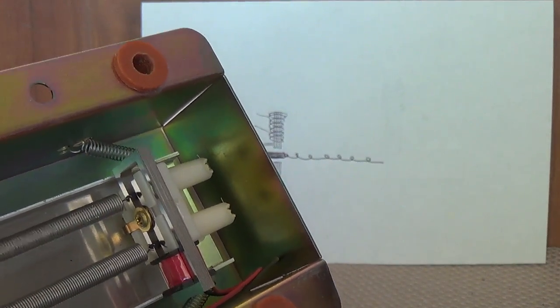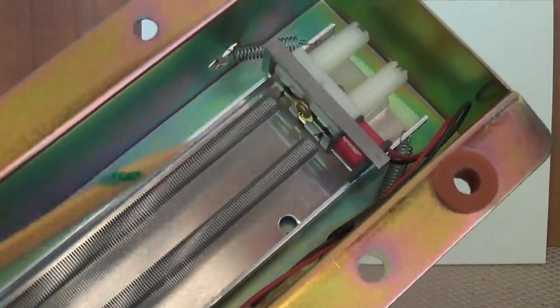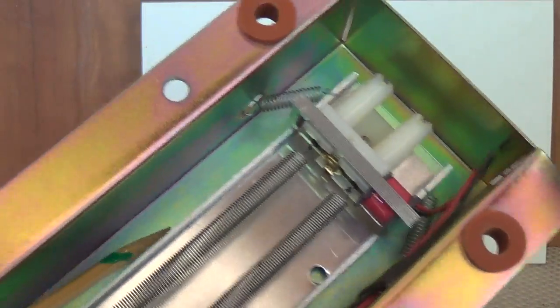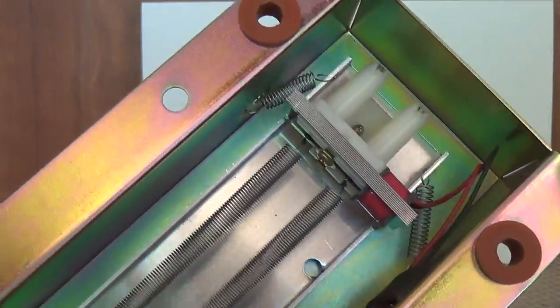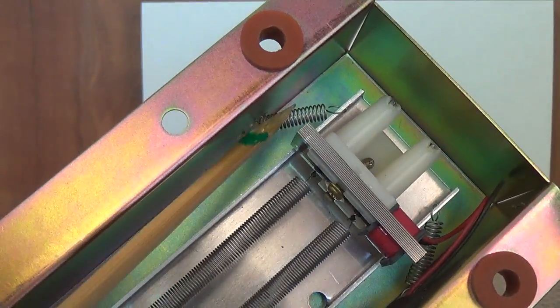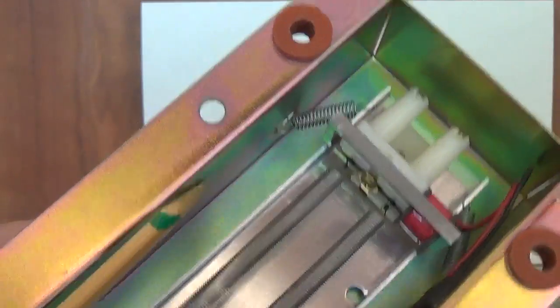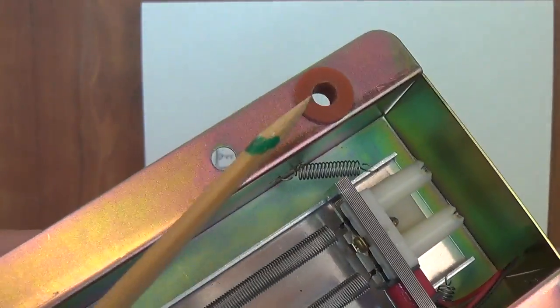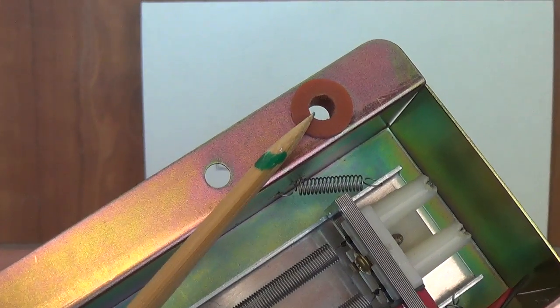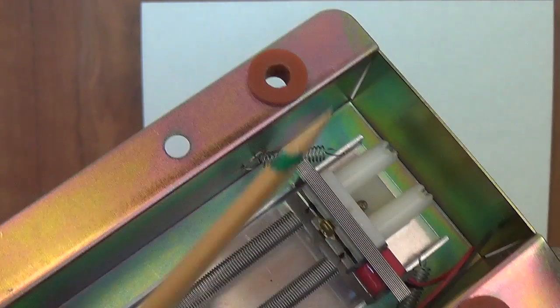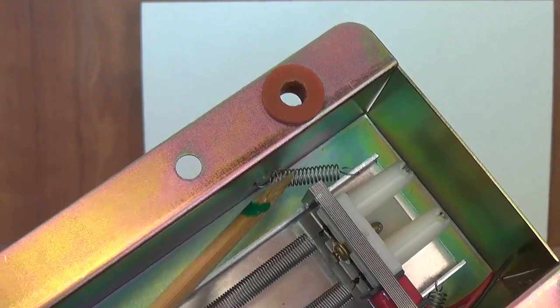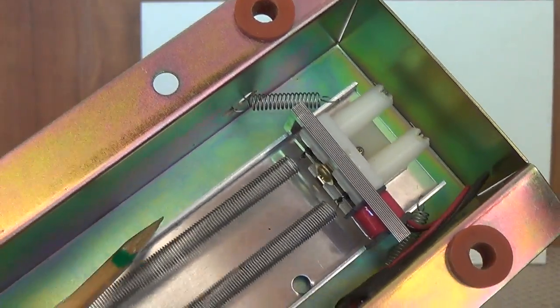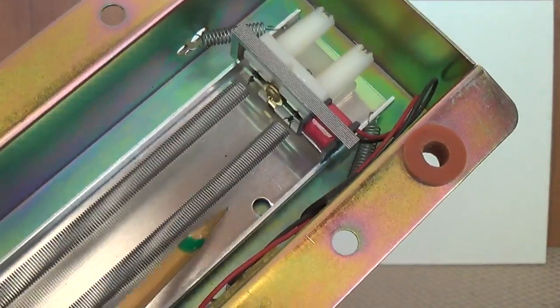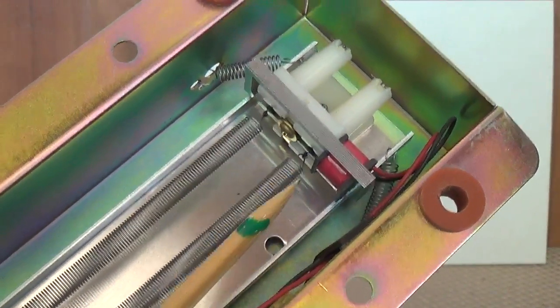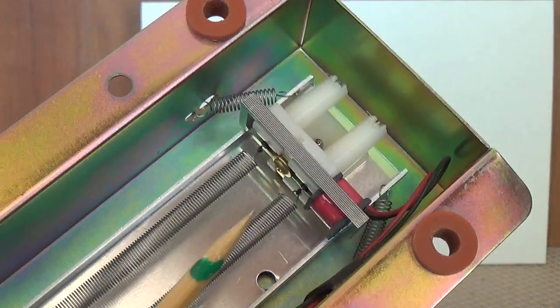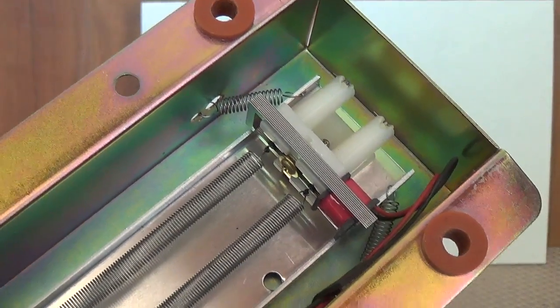We see also, while we're looking in here, that all this takes place on an isolated platform that is spring suspended within the outer metal housing. So we not only have rubber insulation from external vibration, we also have an inner spring-loaded isolation mechanism to keep this unit, the transducer and springs, from being affected by external vibration sources like our old friend the sumo dancer.